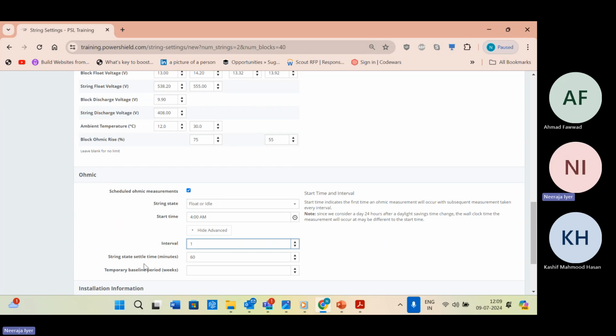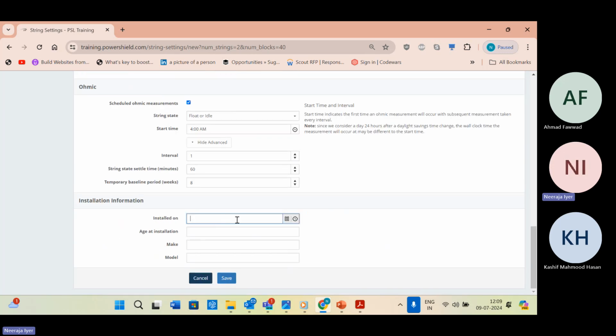String state settle time is there because we are enabling automatic ohmic measurement. We would like to tell the system that, up to 60 minutes, it has to basically check if the system is at float, and only then can it initiate an ohmic measurement. That is the 60 minutes. Baseline is basically, I'm giving 8 to 12 weeks, I'm giving 8 weeks. Baseline is nothing but the threshold for ohmic measurement. There is also system information, like when it was installed, the age of the installation, and the make and model of the batteries. Okay, so you just click save.